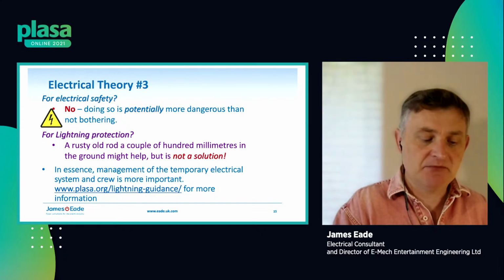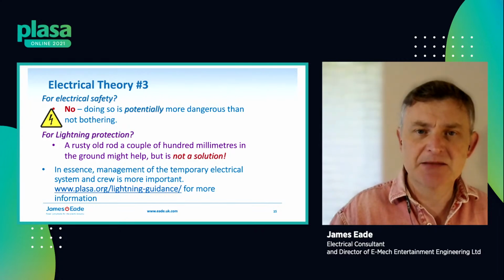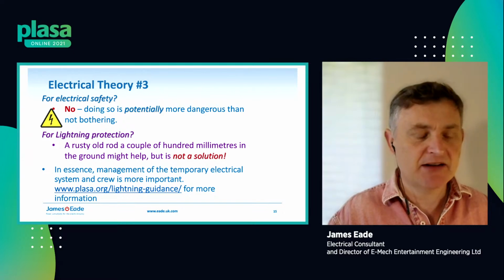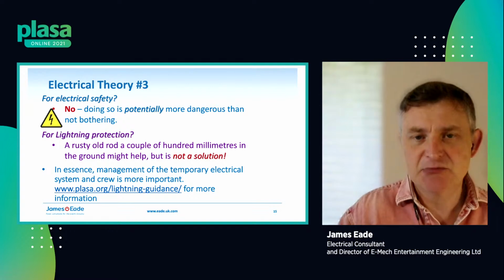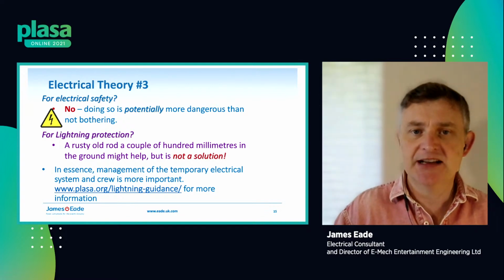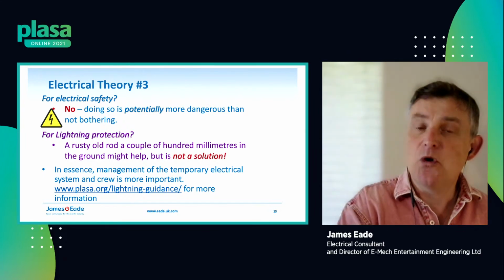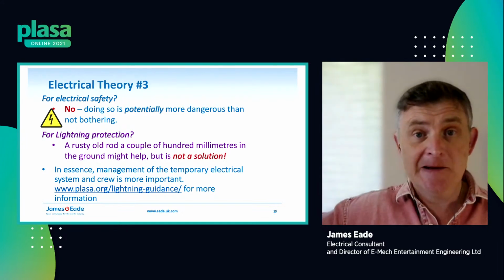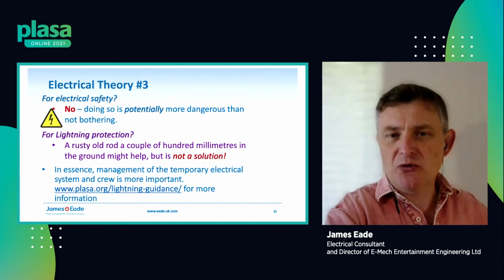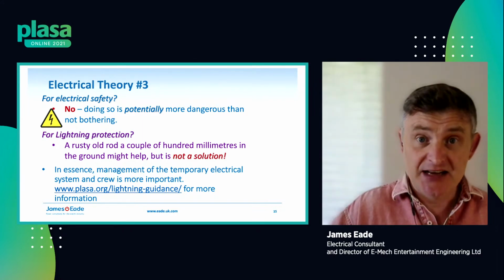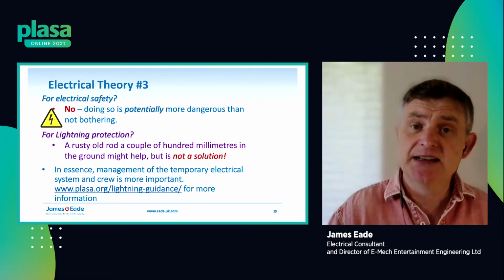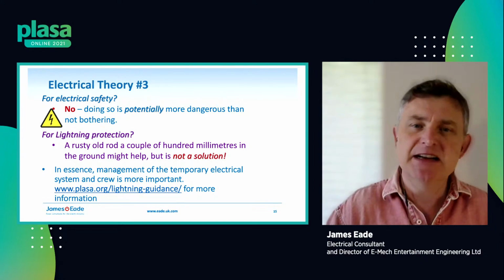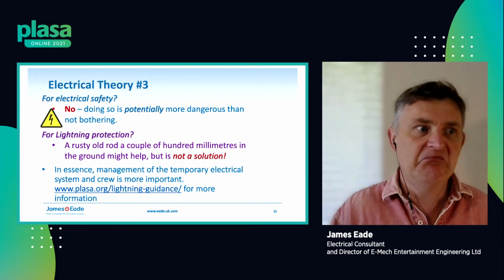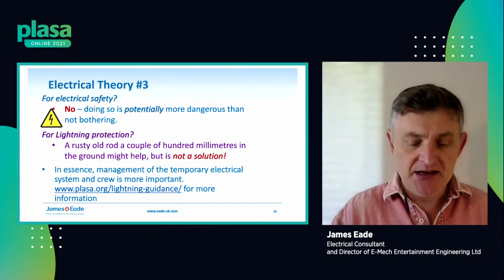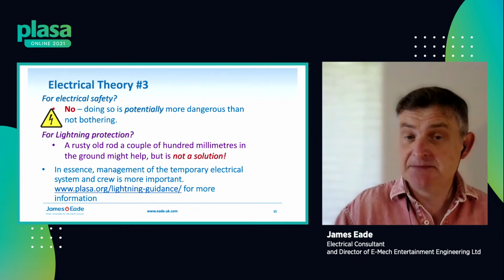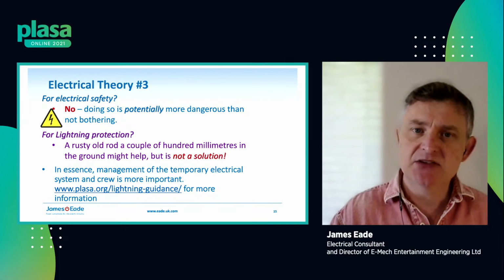What you need to do is, firstly, look at the Purple Guide lightning guidance, which I hope will get more use this coming year as we come out of lockdown. Think about management of your electrical system: if thunderclouds are brewing and the show is put on hold, think about what can be disconnected. If a PA delay tower gets hit, that voltage will propagate through the network, so if you don't need that tower, unplug it and create physical air gaps. Think about putting surge protection in the installation. I hear odd claims like generators attracting lightning, but they don't attract lightning any more than a truck would. It's important to think about management and what you're trying to achieve in keeping the electrical system safe.